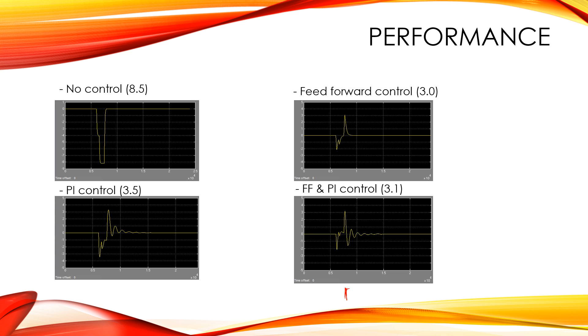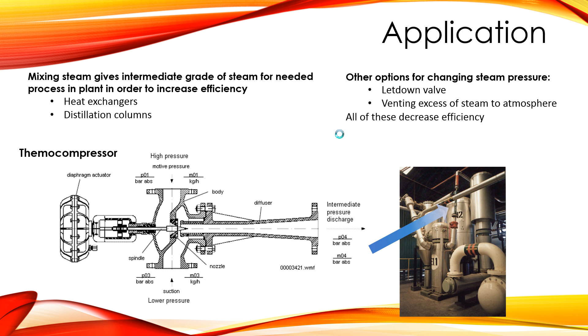So the biggest application for this mixing system is mixing steam for industrial applications. If we mix high pressure and low pressure steam, we get an intermediate grade that can be used for heating many different industrial processes. One device that's used to do that is something called a thermocompressor, that by just changing the valve position like in our system, we can accurately mix the high pressure and low pressure steam to get the steam that we need.